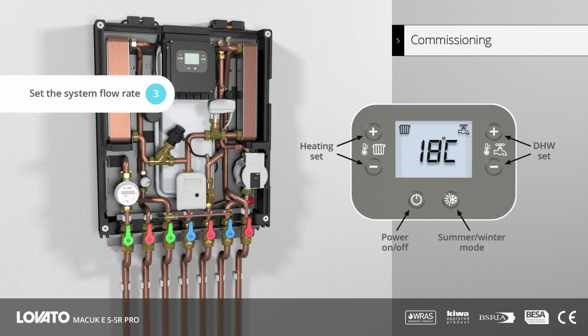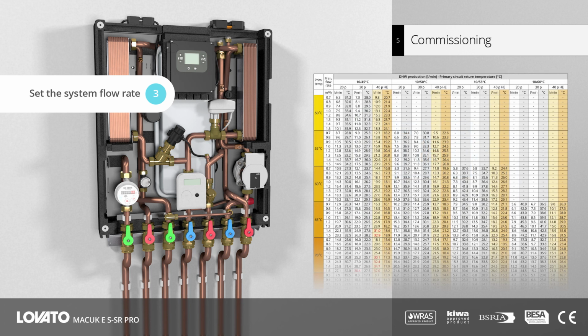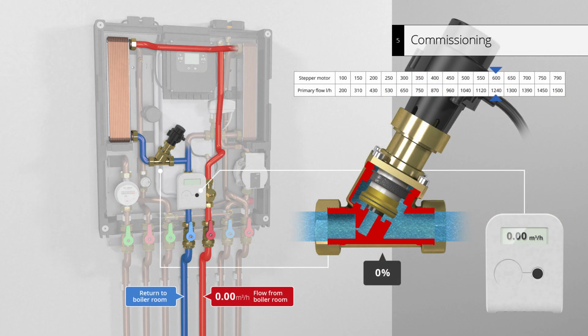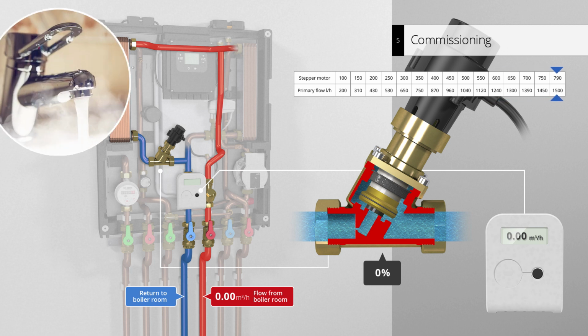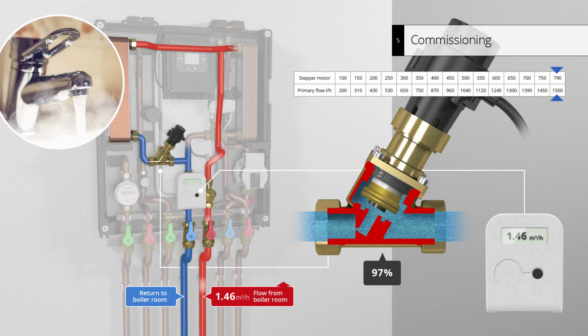Step 3 in commissioning the system is to balance and set the system flow rate. For this example, based on a primary flow temperature of 60 degrees and a primary flow rate of 1500 litres per hour, a 40 PHE system will be configured to supply 22.9 litres per minute at 50 degrees Celsius. Firstly, via the control panel, access the stepper motor setup menu and adjust the value from the factory set 600 to 790. Next, fully open all hot water taps and allow to run.